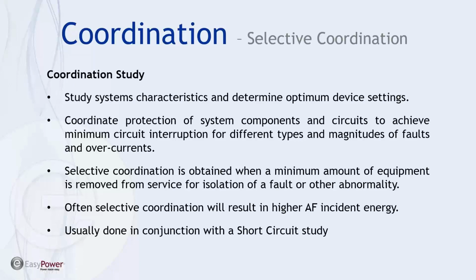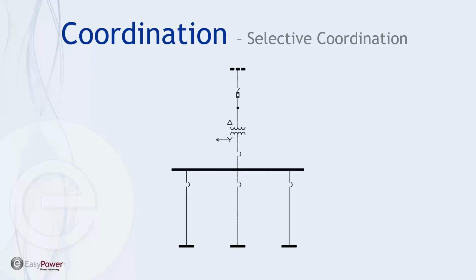Coordination, again, potentially means higher incident energy, especially at the upper elements, because we're having to set their timing slower to allow the downstream elements to work first. And it goes without saying that this is usually done in conjunction with a short circuit study. So here's how something like this works.